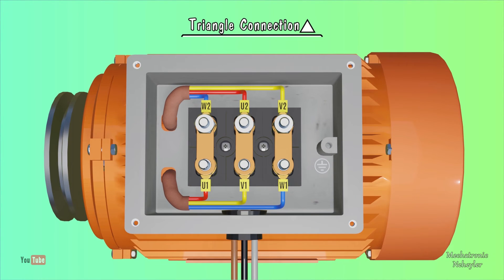The external line cables reach the three-phase motor box to connect to the corresponding terminals. In such a way that L1 is connected to terminal U1, L2 is connected to terminal V1, and L3 to terminal W1.